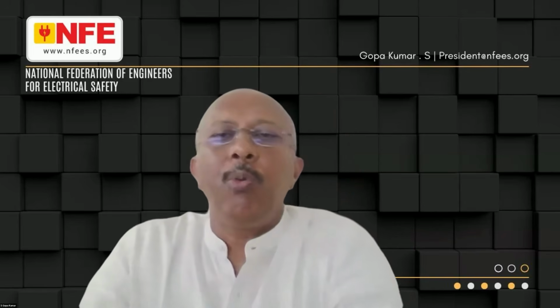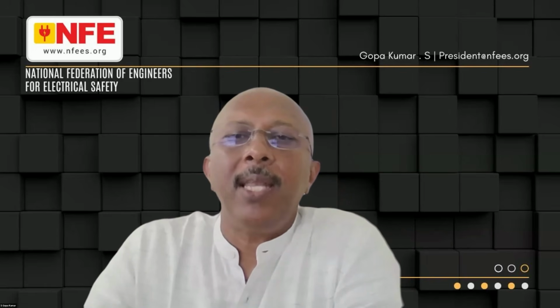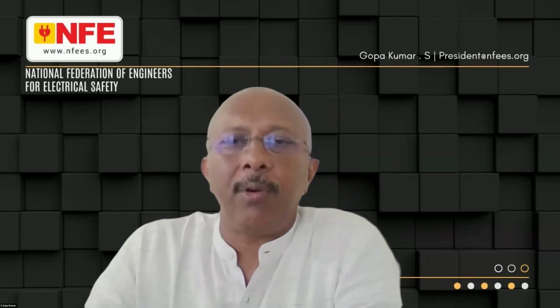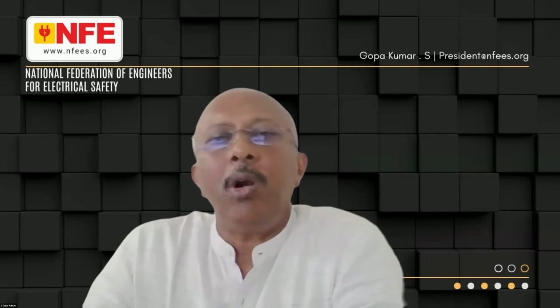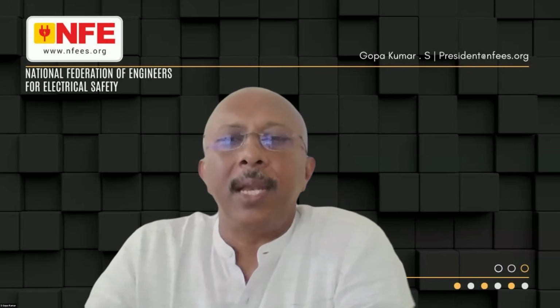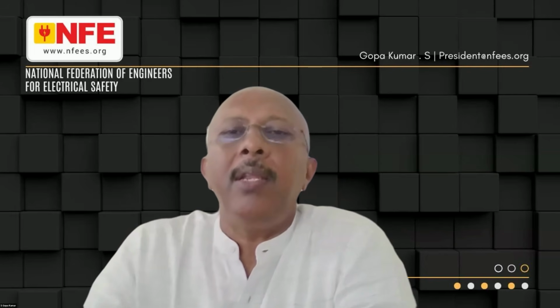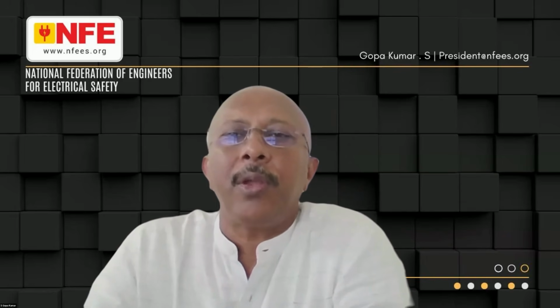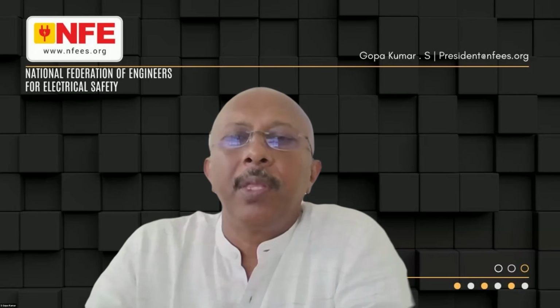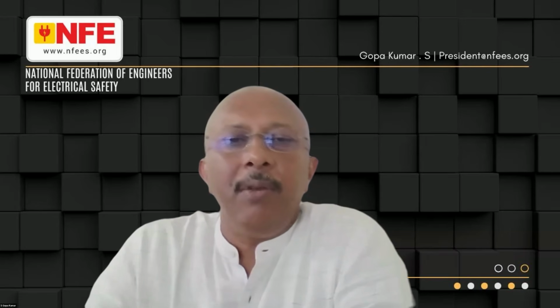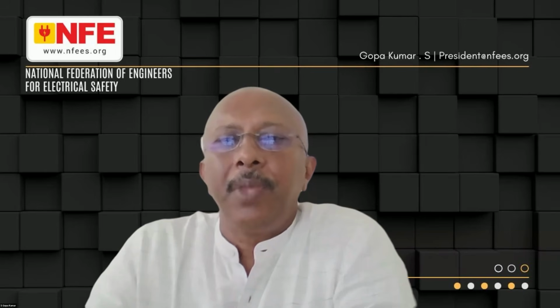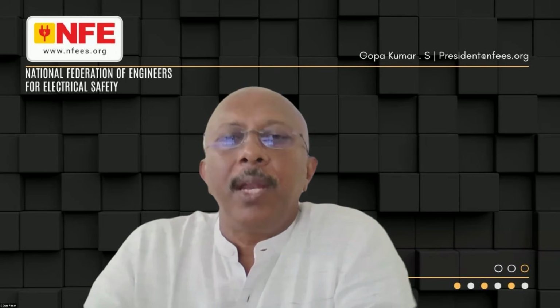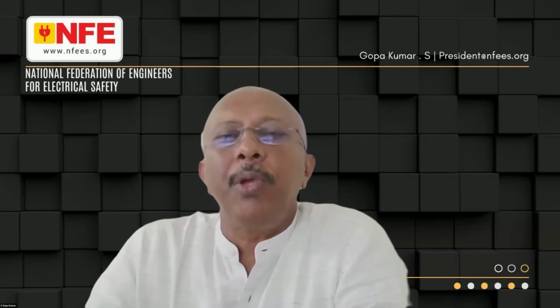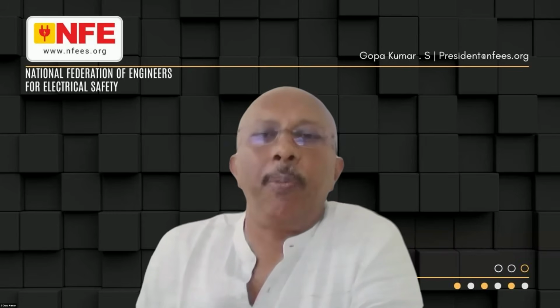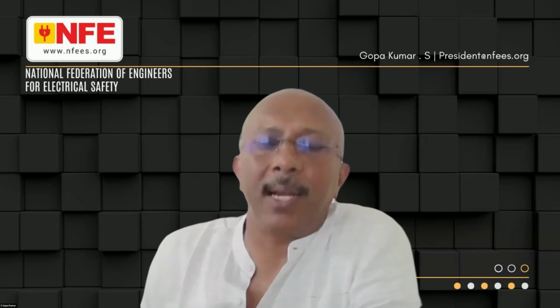So, Mr. Prasad Patnaik asks, how to prevent a short circuit in hospitals, as most of the fires take place in ICUs and the storage rooms due to short circuit? Please note that short circuits may happen in an electrical installation. It can happen because if you have deteriorated equipment, after some time it can create a short circuit. Short circuit is not the problem. Automatic disconnection is the problem. In case of a short circuit, protection against thermal effect means that during normal or abnormal operation of an electrical installation, once the temperature goes beyond a certain limit, the protective device should operate and the faulty circuit has to be disconnected.